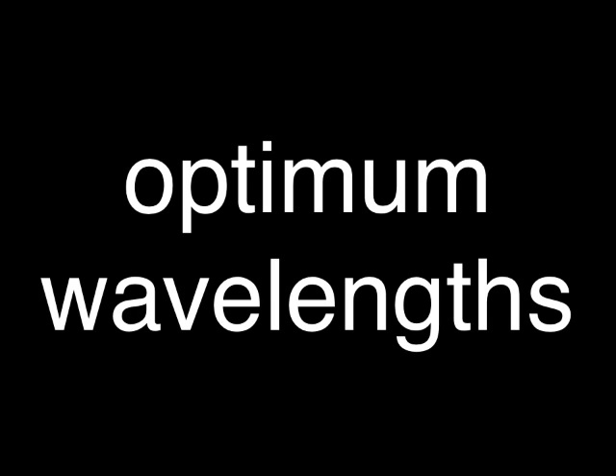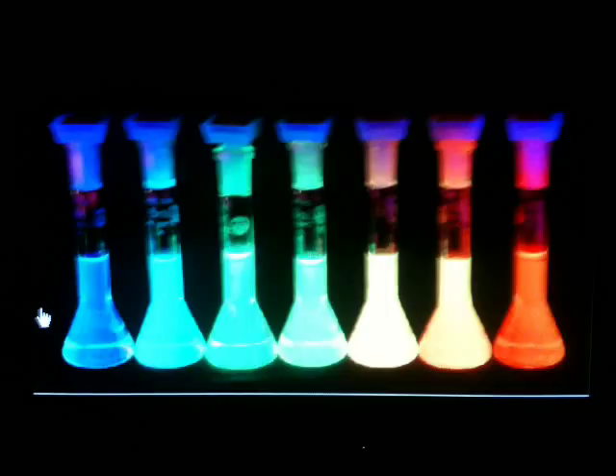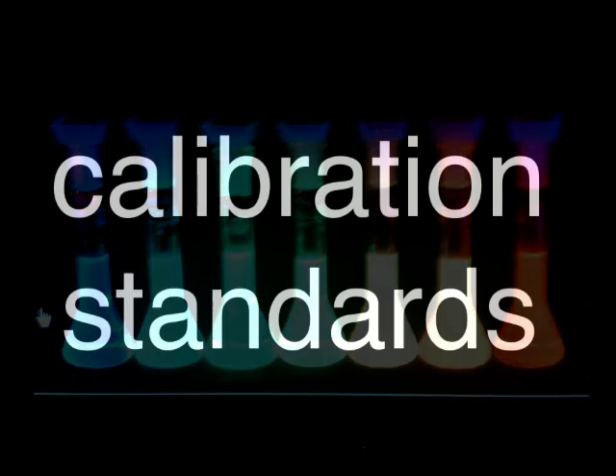The next step in calibration will be finding the optimum excitation and emission wavelengths. This is simple by setting the machine to scan your analyte for the excitation and emission wavelengths. Once you get that spectra, you will simply use the peak of both wavelengths. These peaks will give you the best and most intense fluorescent readings possible, which can be very bright.